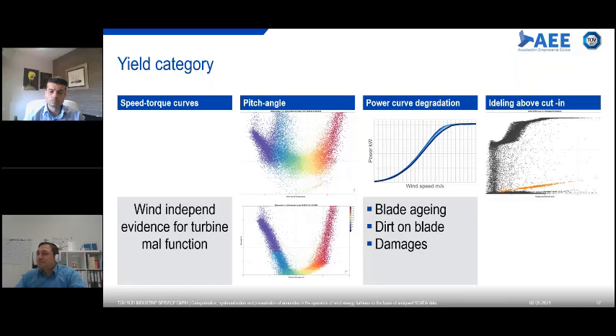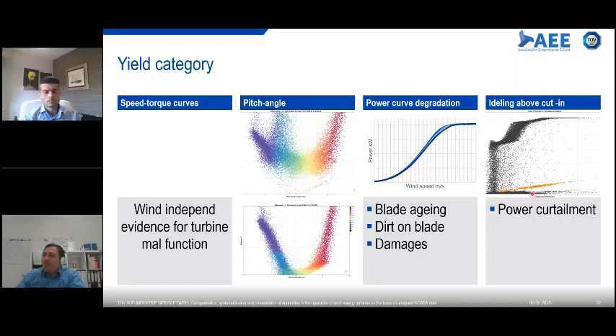Another example, which is also quite obviously visible, is a power curtailment, especially when you're not aware of it. Here we see wind speed above cut-in, where my turbine is usually operating, and here the generator RPM. At about 10 to 15 meters, we should see the wind at full speed on the generator, so not much deviation. But then we see this curve down here, marked to make it more visible—the turbine is idling, when it's not supposed to be.